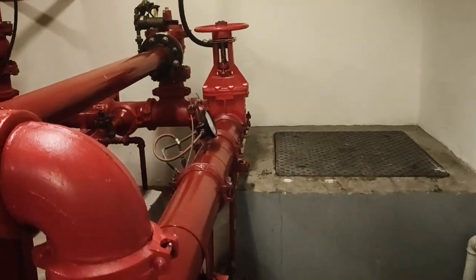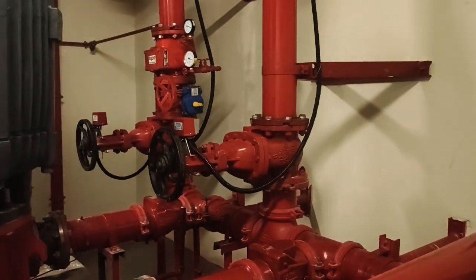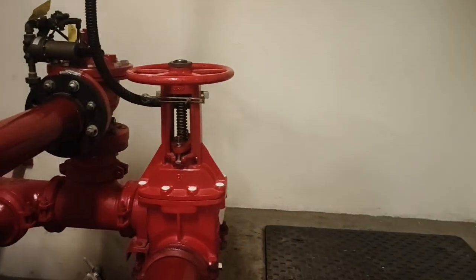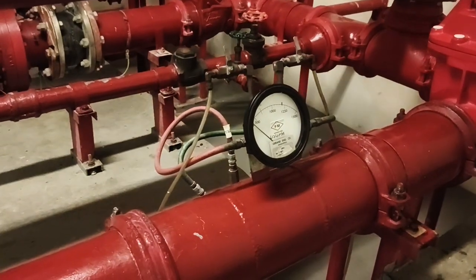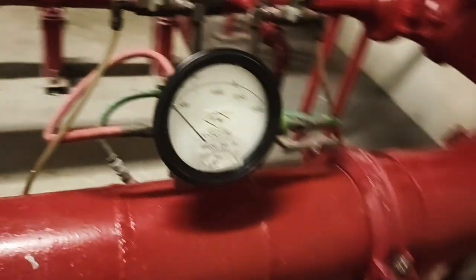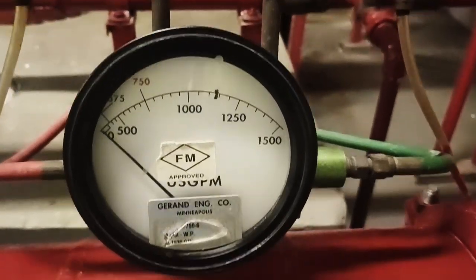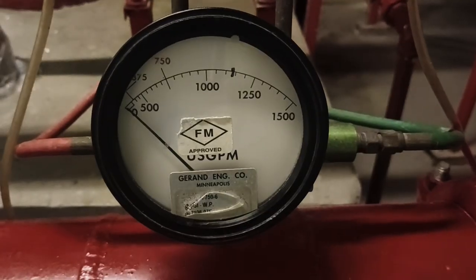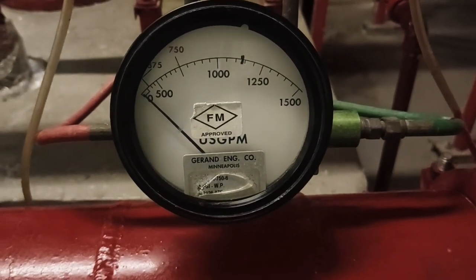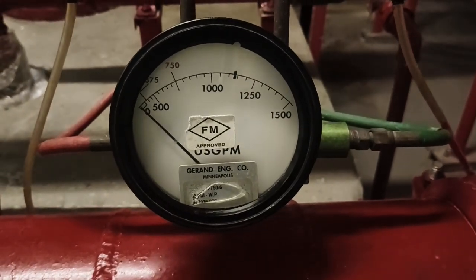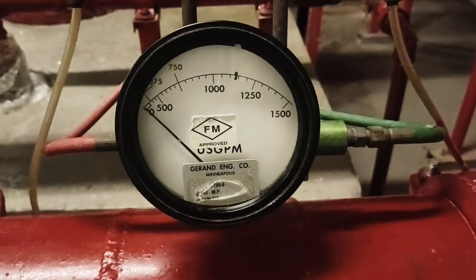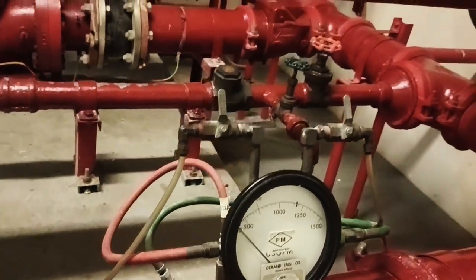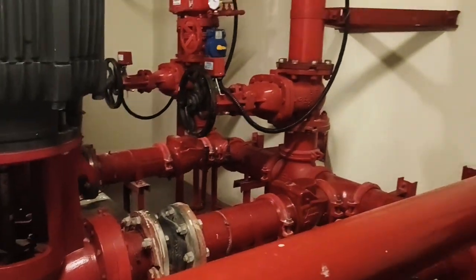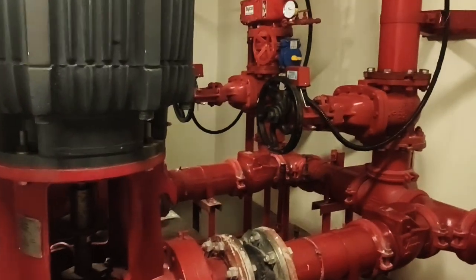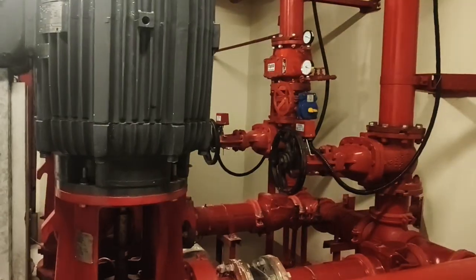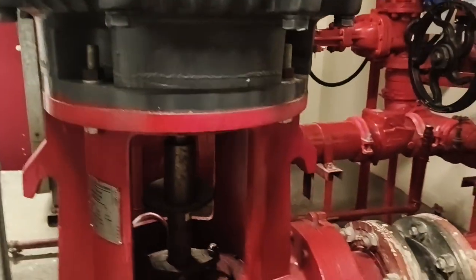So during testing, what we have to do is close the hydrant line, close the main discharge line, then we can use the test line to do the testing. From this you can tell the GPM of this pump. So let me know in the comment section if you know the GPM for this pump by looking at the flow meter, because the flow meter has to be in line with the GPM of the pump. All right, so this is the shaft.